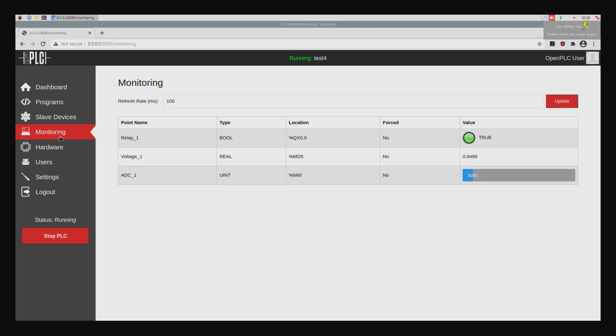You will see it turn on, turn off, on and off, fluctuating between 0 bar and 0.2 bar, trying to maintain anywhere in between. It will not exceed this range — the PLC will ensure that under no circumstance does the pressure exceed 0.2 bar. So you will hear a lot of relay chatter as the pressure increases, it switches off, and so on.